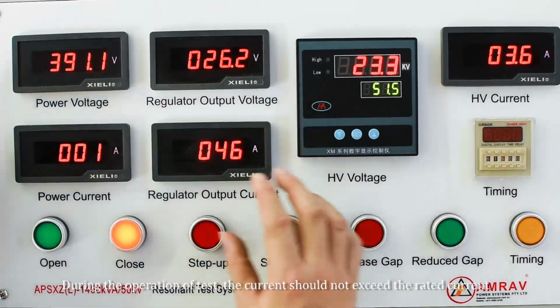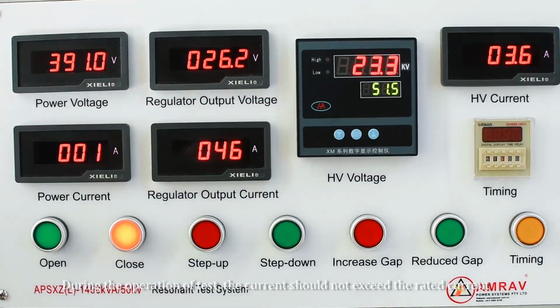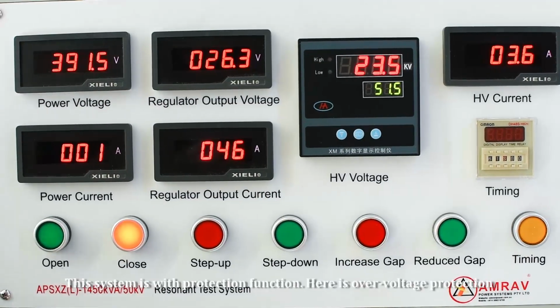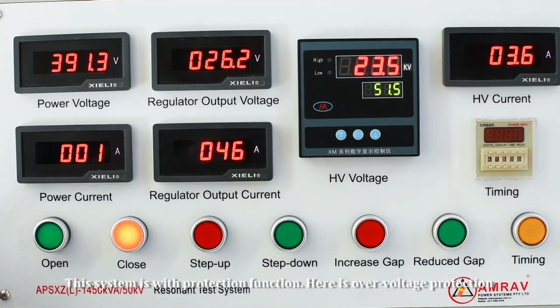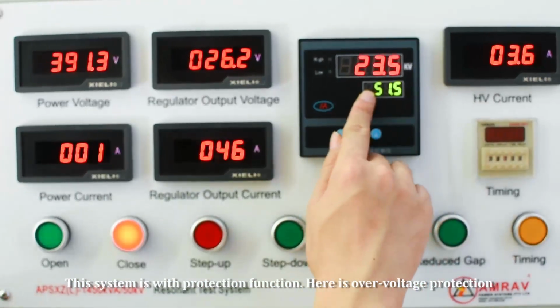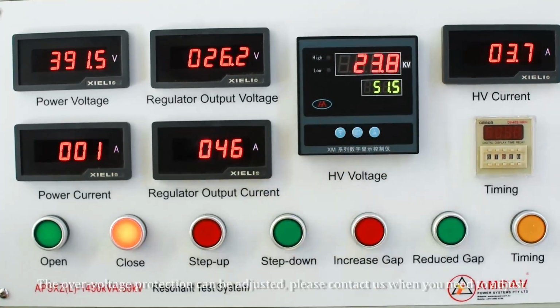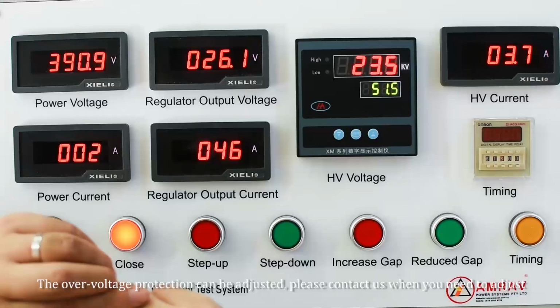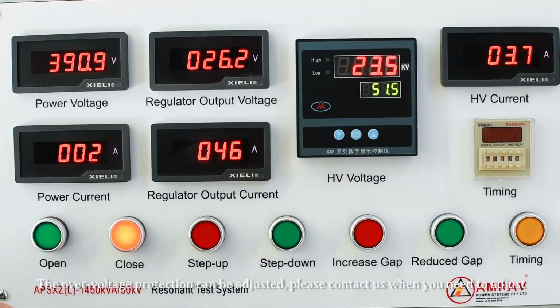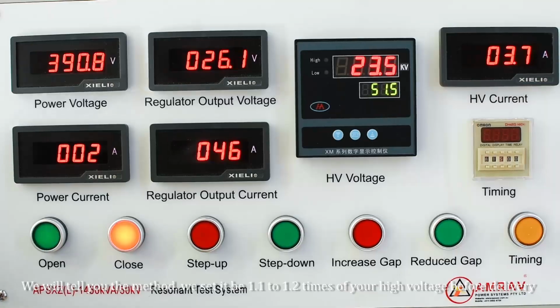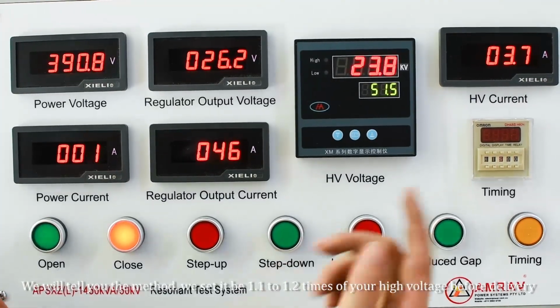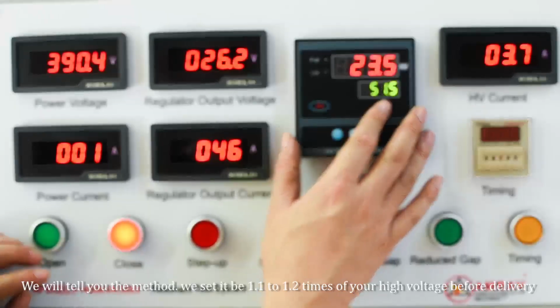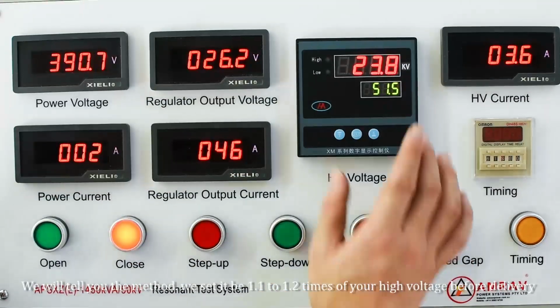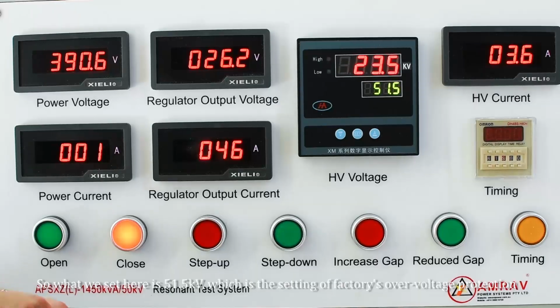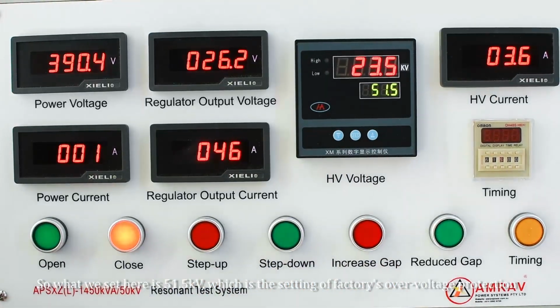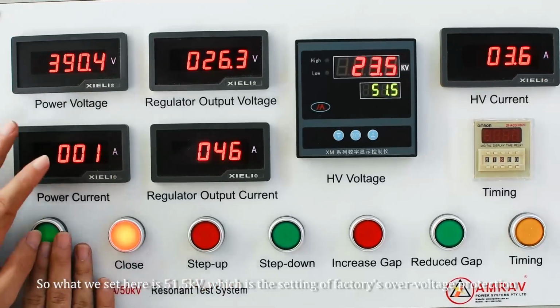During the operation of the test, the current should not exceed the rated current. This system has a protection function. Here is overvoltage protection. The overvoltage protection can be adjusted. Please contact us when you need to adjust. We will tell you the method. We set it to be 1.1 to 1.2 times of your high voltage before delivery. So what we set here is 51.5 kV, which is the factory setting of overvoltage protection.